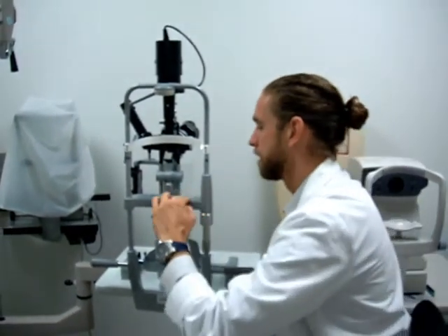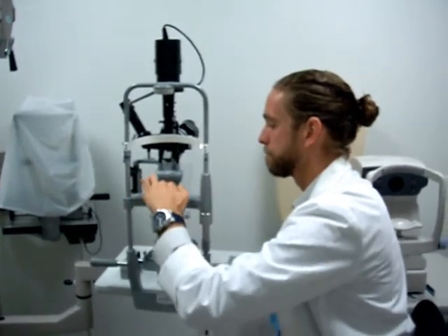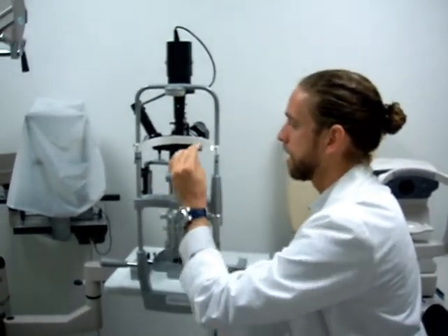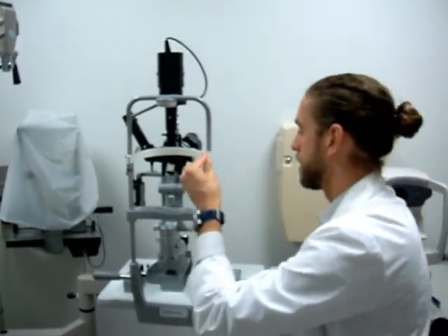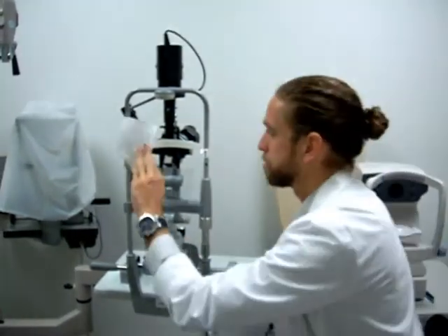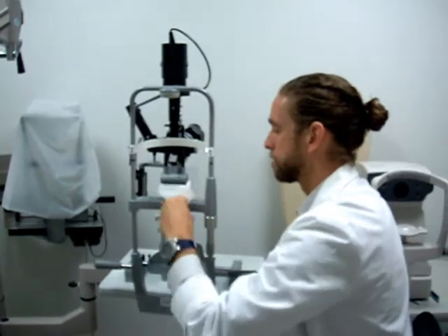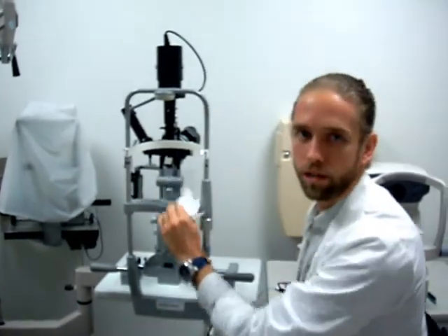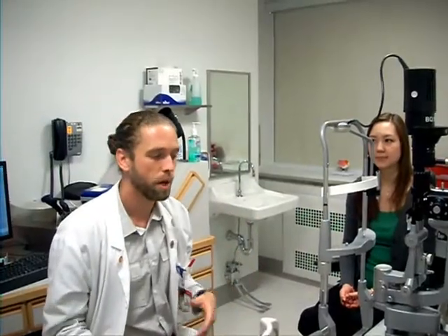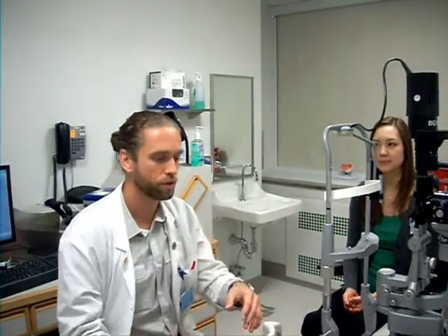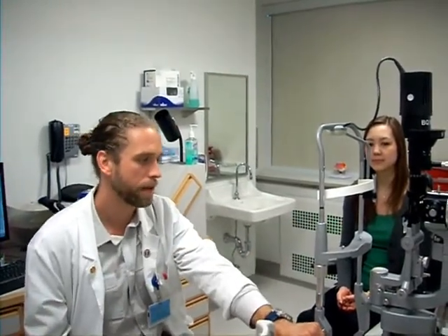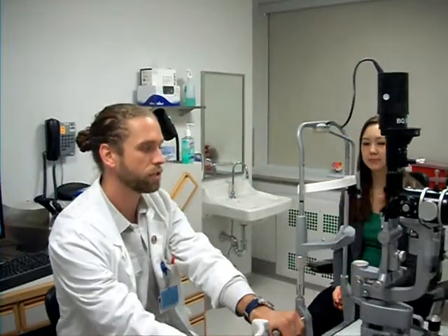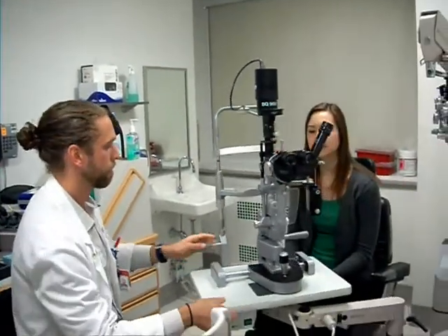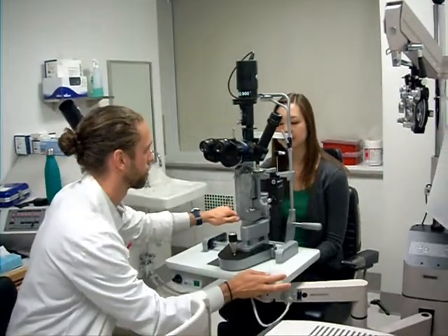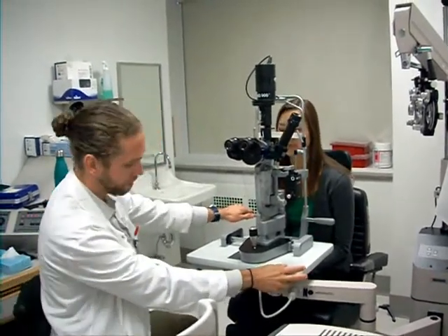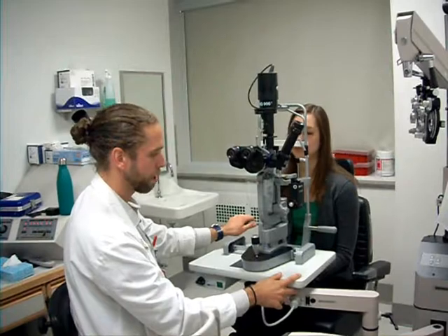So you just want to take an alcohol wipe, rub down the chin area and the forehead. And just to expedite the process, you can take a tissue as well. Get that dry, just so the patient doesn't have anything wet touching their face. Now you're ready to approximate the machine to the patient. So first thing you want to do is make sure that the machine is not locked, and swing it across the front of the patient and approach them in a slow manner, making sure not to hit their knees or their arms in the process.